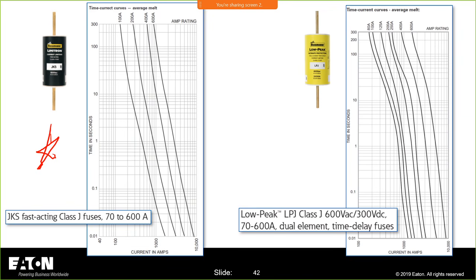So there was a question about, can you explain real quick why all fuses are not current limiting? The reason is because you have that class H fuse. It's just a lower cost fuse for when you don't need current limiting or you're not intended to have it. It's used primarily in your HVAC world and things of that nature. But that fuse, the way it's designed, is not current limiting in nature. Your other fuses are pretty much all current limiting in nature because it's just the way physics works out, with all of the pinch points and how it's constructed.